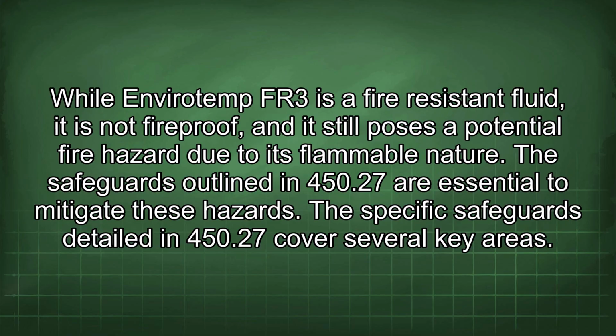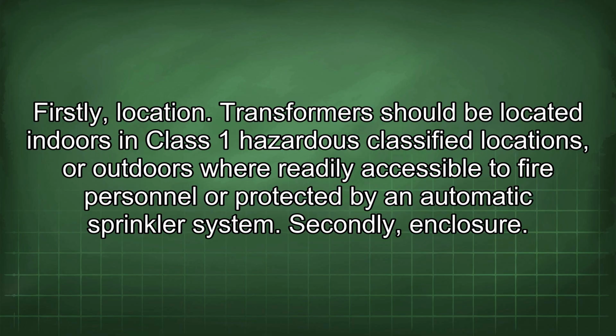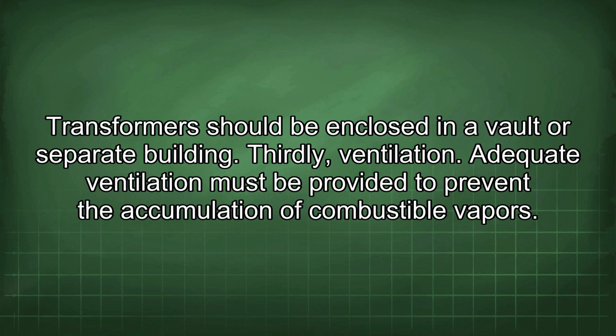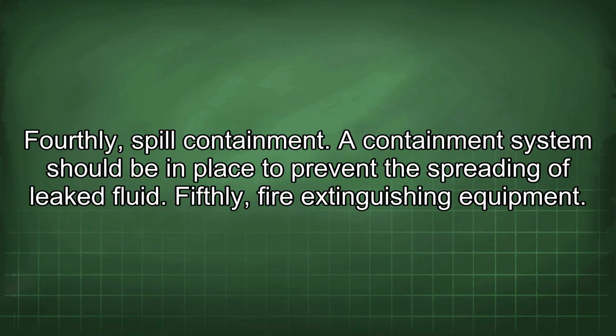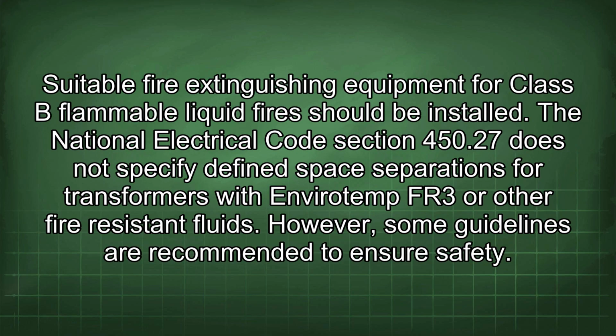The specific safeguards detailed in 450.27 cover several key areas. Firstly, location. Transformers should be located indoors in Class 1 hazardous classified locations or outdoors where readily accessible to fire personnel or protected by an automatic sprinkler system. Secondly, enclosure. Transformers should be enclosed in a vault or separate building. Thirdly, ventilation. Adequate ventilation must be provided to prevent the accumulation of combustible vapors. Fourthly, spill containment. A containment system should be in place to prevent the spreading of leaked fluid. Fifthly, fire extinguishing equipment. Suitable fire extinguishing equipment for Class B flammable liquid fire should be installed.